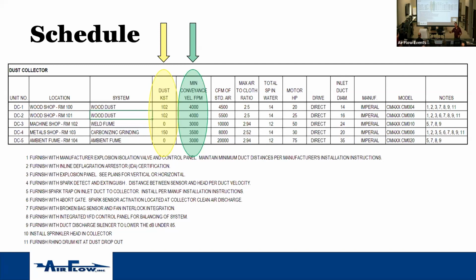Our collector, when it shows up, will also have the KST listed on the tag. So in the future, if somebody wants to come through and add on or pick up more points in their dust system, they've got to get the dust tested and make sure we stay below that KST level.